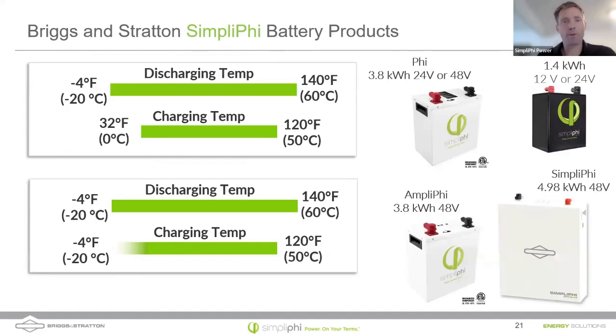Let's talk a little bit about temperature. So first, I'm going to address the Phi batteries. So the small format Phi battery, as well as the larger format 48 or 24 volt Phi batteries. Their discharging temperature, they can be discharged safely down to -4 degrees Fahrenheit and all the way up to 140. So on the Celsius scale, that's -20 Celsius up to +60. On the charging side of things, the range is a little bit reduced. And so charging is reduced from 0 degrees Celsius up to 50 degrees Celsius.